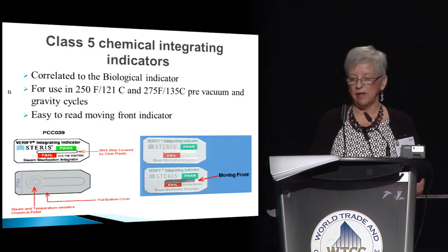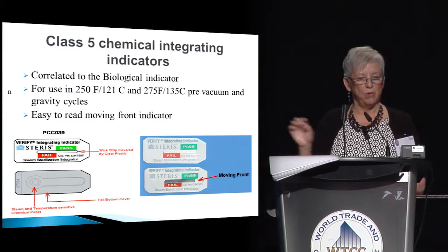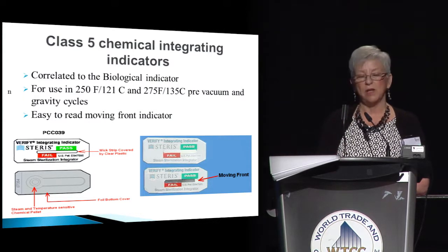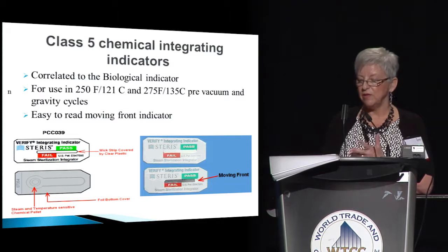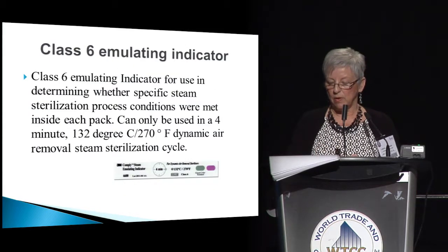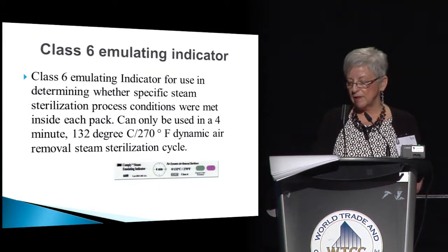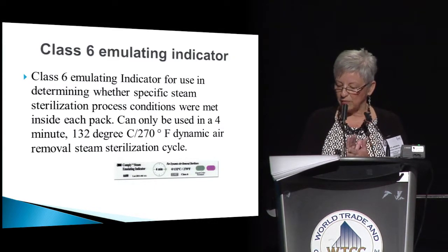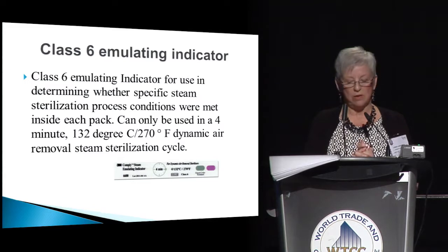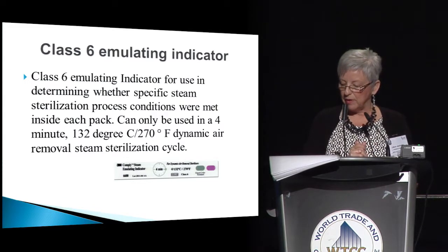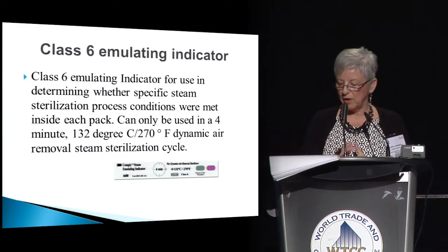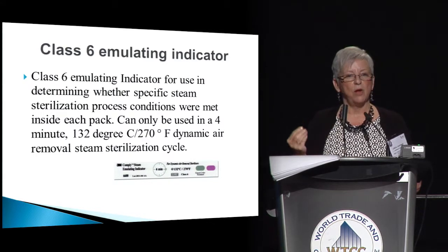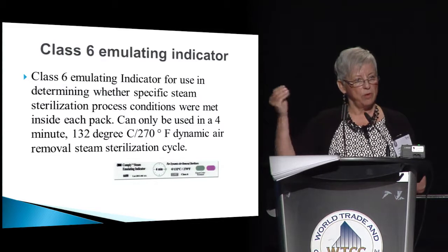You can see on the slide that if it moves or it doesn't move, you've got a fail. So you can really tell if it's an easier indicator to move. The next is Class 6, and it's an emulating indicator. Because they are not required to correlate to the BI, they do not perform as a BI. So if you're using the Class 6 emulator, it's going to respond to a lower temperature where your BI will be more of a challenge.